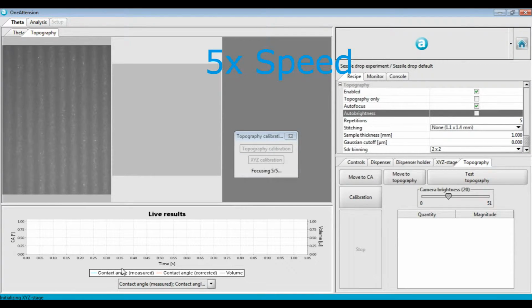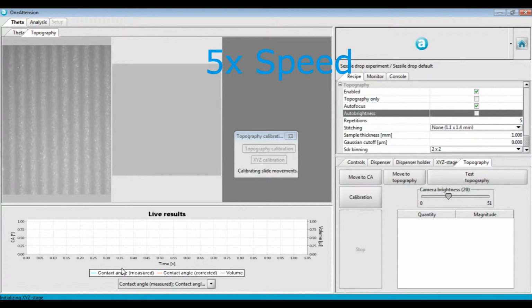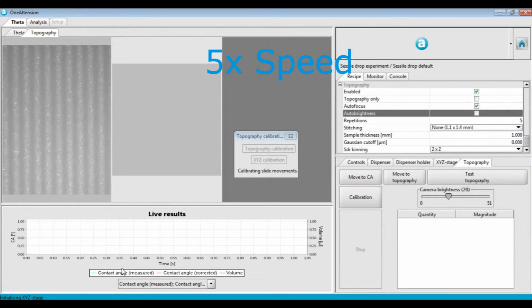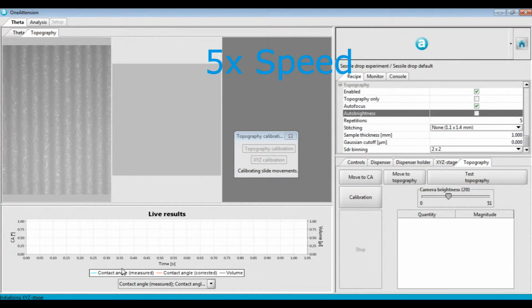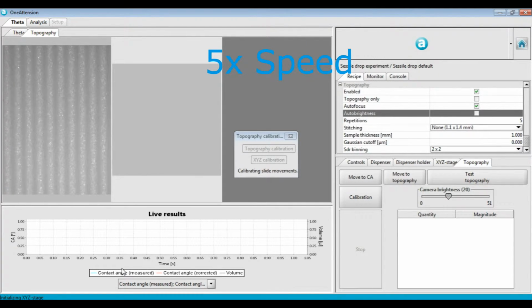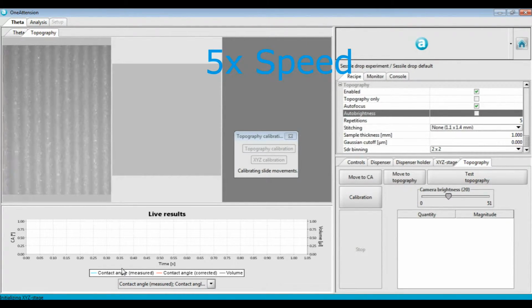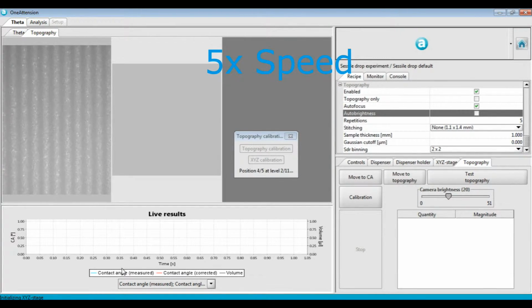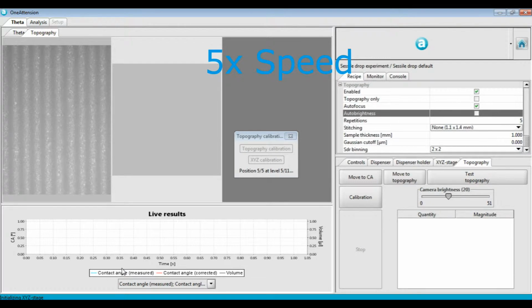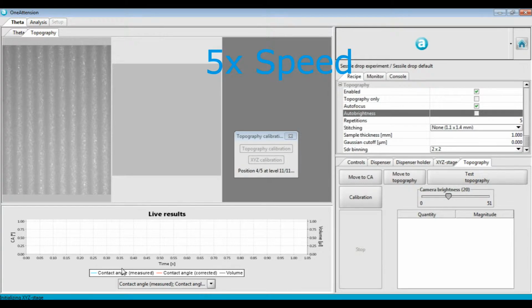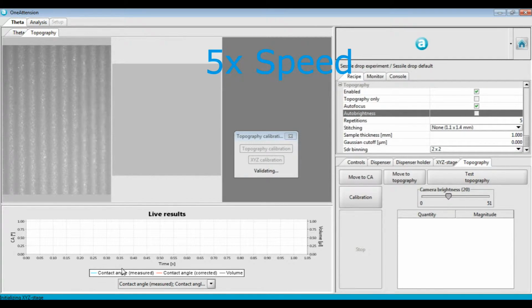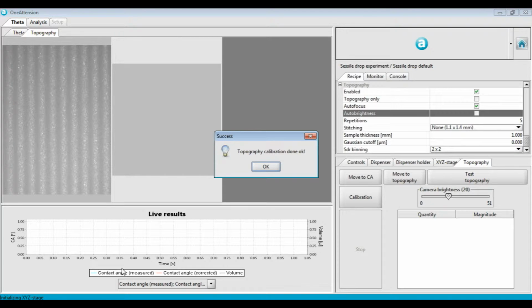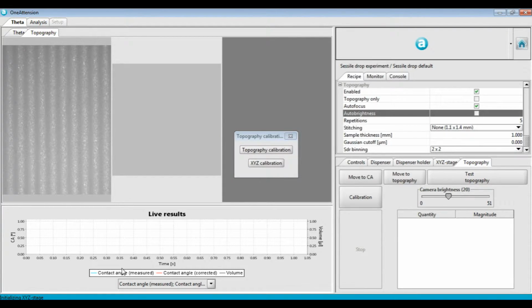If there are any white pixels or areas on those image maps, it means that the topography module was not able to resolve the height at those pixels. Sometimes if your sample is extremely rough at those positions, that can cause the camera to not be able to resolve them. Other times it can be because the topography calibration didn't quite work. And so if you see a lot of your samples, when you're taking these measurements, have those white spots, consider redoing just the topography part of the calibration. And now the topography calibration is complete.